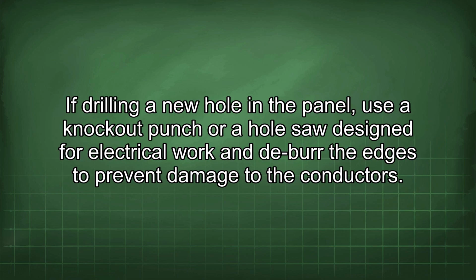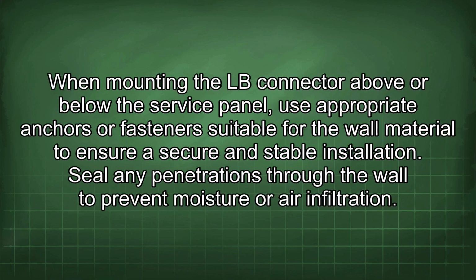If drilling a new hole in the panel, use a knockout punch or a hole saw designed for electrical work and de-burr the edges to prevent damage to the conductors. When mounting the LB connector above or below the service panel, use appropriate anchors or fasteners suitable for the wall material to ensure secure and stable installation. Seal any penetrations through the wall to prevent moisture or air infiltration.